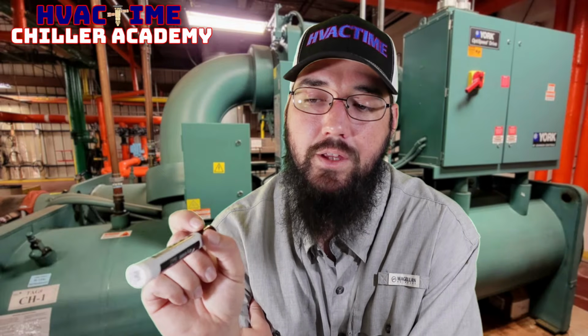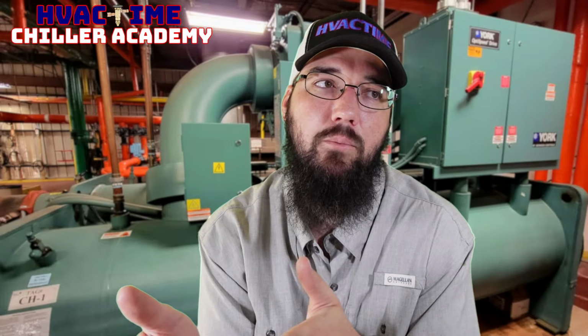Does approach change when you have one circuit on or two circuits on? So yes, the approach value. Let's say if you have a two circuit machine and only one circuit is running, the second circuit turns on and now you've got both circuits together. They do affect each other because both circuits are now sharing that heat, and the approach value will shift a little bit. You will see a little bit of a shift in the approach, and I can give an example of this. But let me finish your question. But the technicality of why does approach decrease when load decreases? Amazing question. Yes, amazing question.